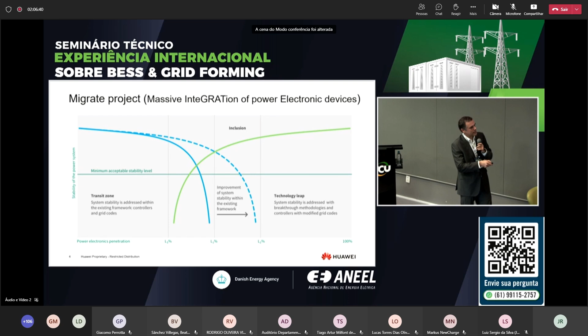So thinking about Spain, and take into account this is 2005, a long time ago — this is the origin of the first grid code, at least the first one I know of. In Spain, if there is a three-phase fault here, you see the voltage go from 0 to rated voltage. If there is a fault here — and you know Spain is very small compared to Brazil, but this is maybe 200-something kilometers — and if there are a lot of wind turbines here and there's a fault, without fault ride-through you will lose a lot of power instantaneously.